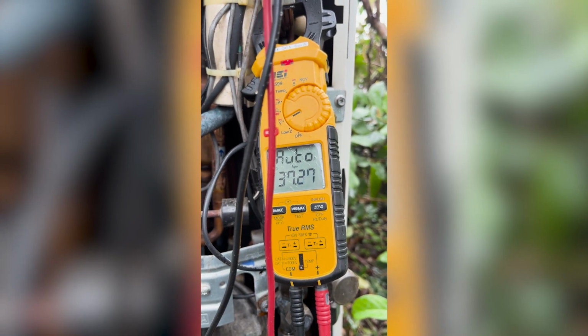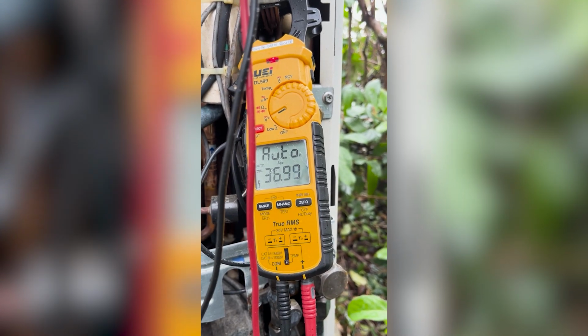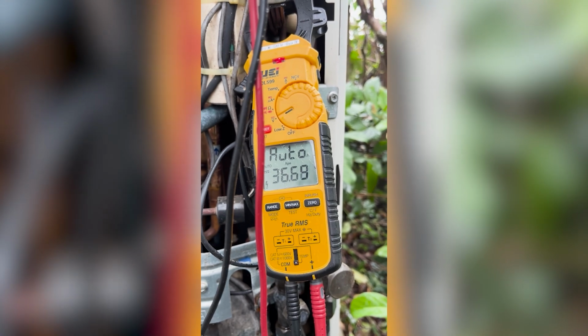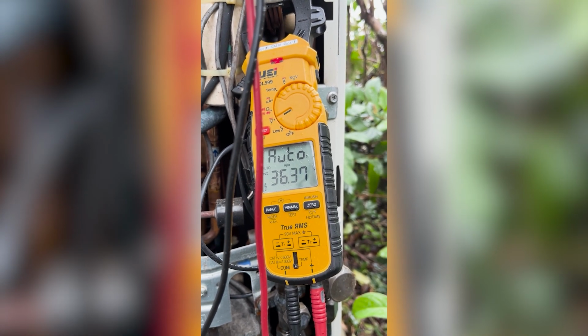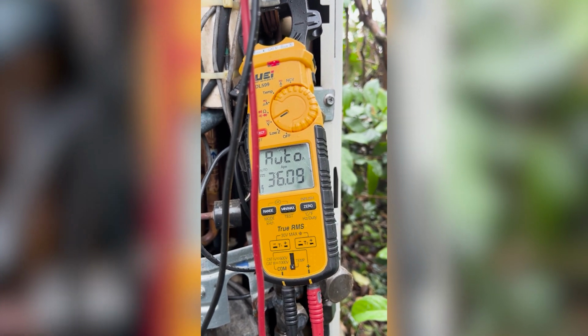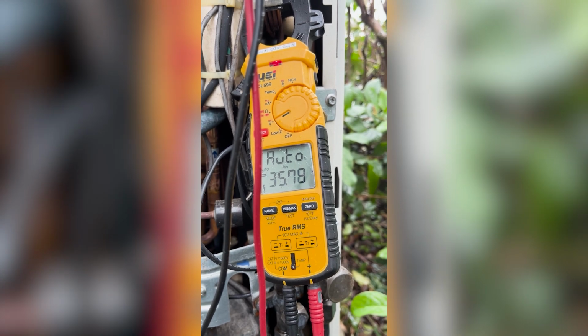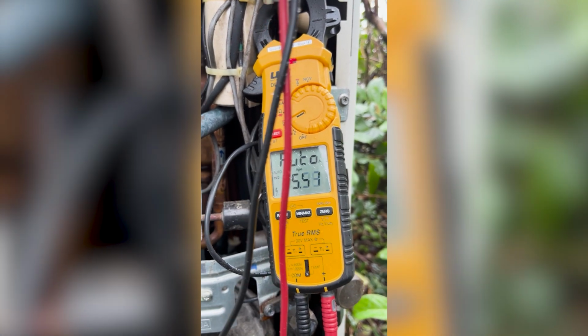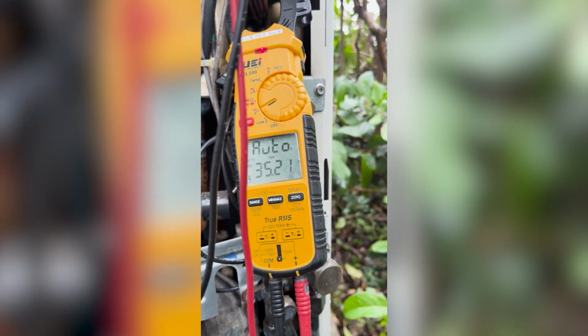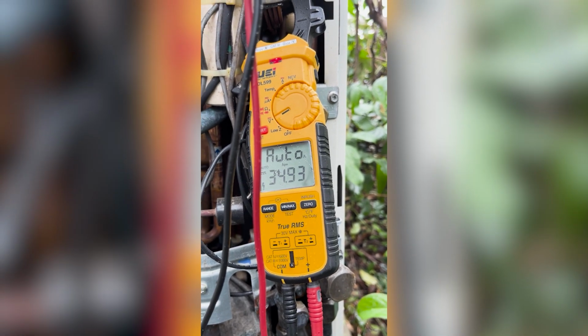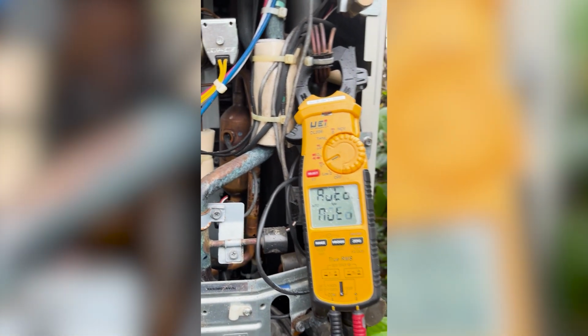And so, you know, residential equipment, we always want to be safe around capacitors, but for inverter equipment especially, you're going to always want to check that C plus, C minus at the capacitors to ensure that they are below 50 volts, or my rule of thumb is usually 35. And as you can see now, I'm okay to work on this piece of equipment and troubleshoot it. So that's my safety tip of the day.